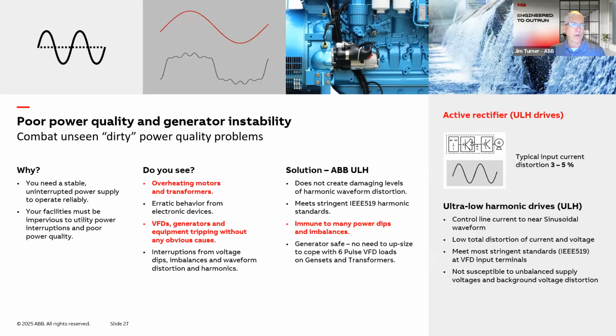However, one easy way to cope with this in the specific application is to apply one of our active front end variable frequency drives in place of 6-pulse drives. This style of drive, active front end, compensates for input voltage fluctuations and doesn't create harmonic distortions like other 6-pulse drives do. Our water application experts can explain more about the technical details of how this technology works and how it counteracts the negative impacts of poor power quality.